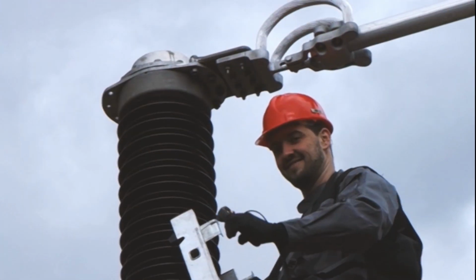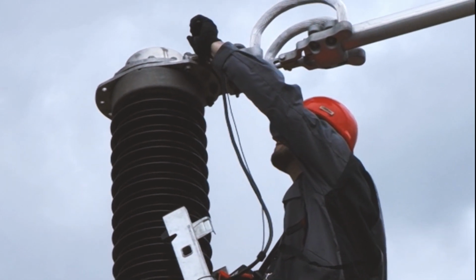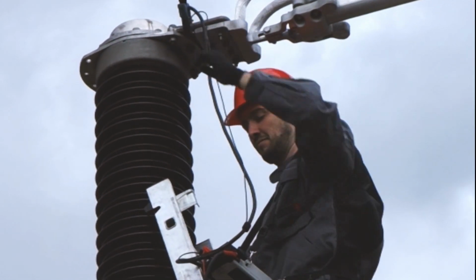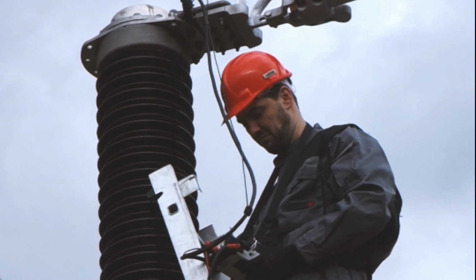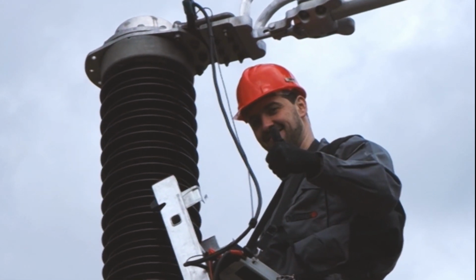One operator is sufficient to perform the test, since the measurement is done directly on the breaking chamber terminals. There is also no need to use long and heavy test leads.